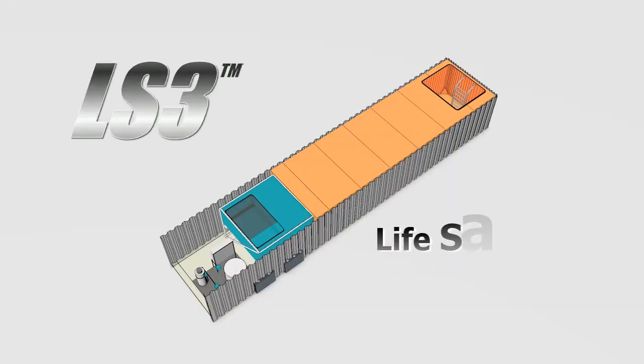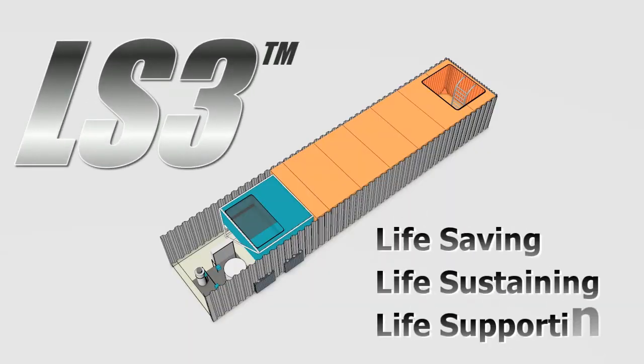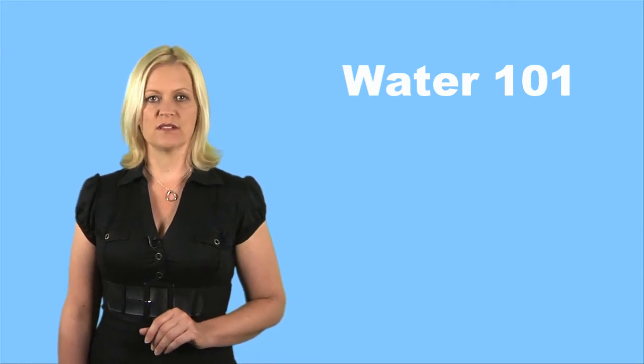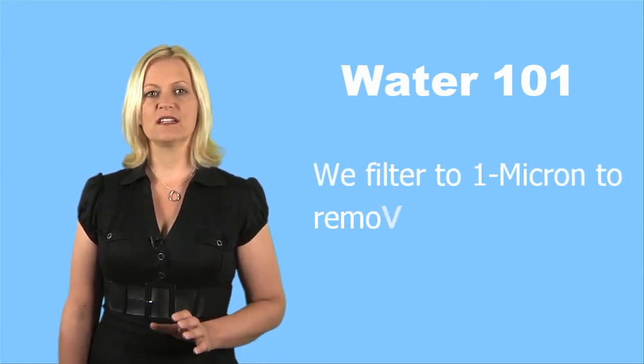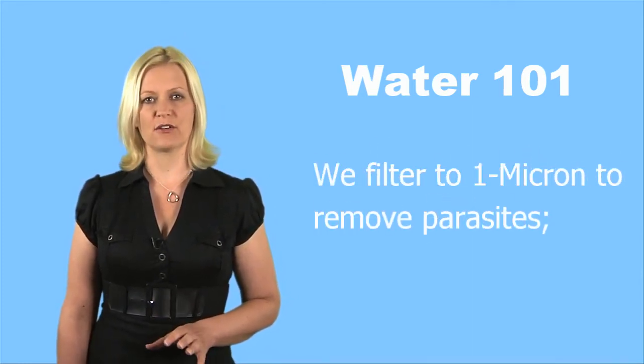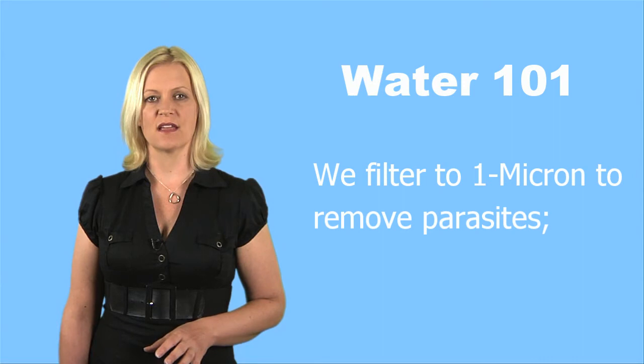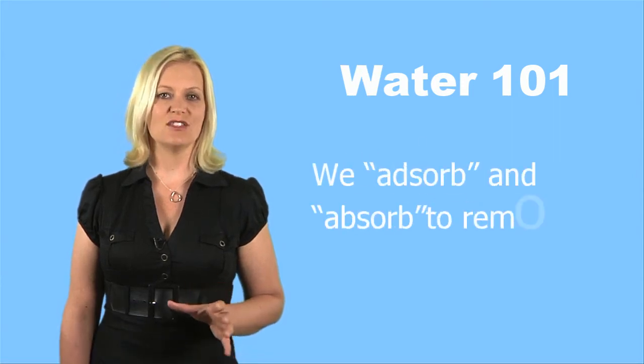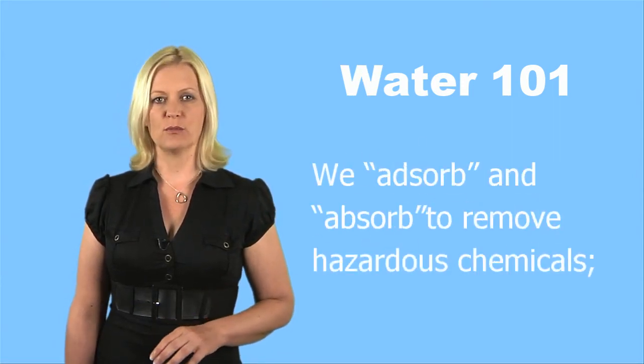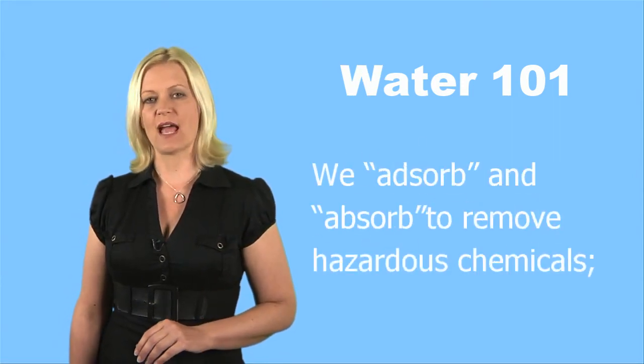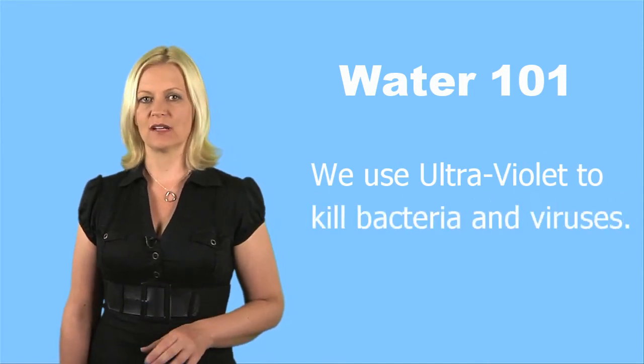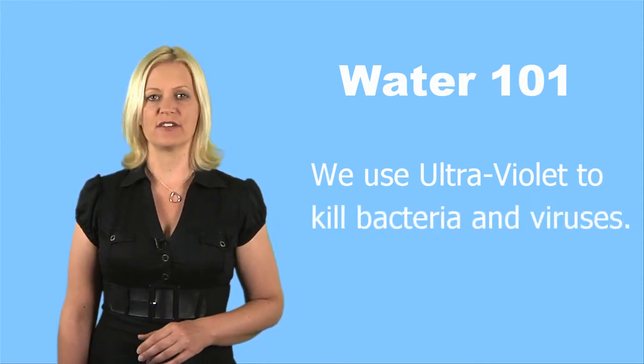The effluent that clears through the recycler now enters the global LS3 water purification process. This is basic water 101. We filter to 1 micron to remove parasites, we adsorb and absorb to remove hazardous chemicals, and we use ultraviolet to kill bacteria and viruses.